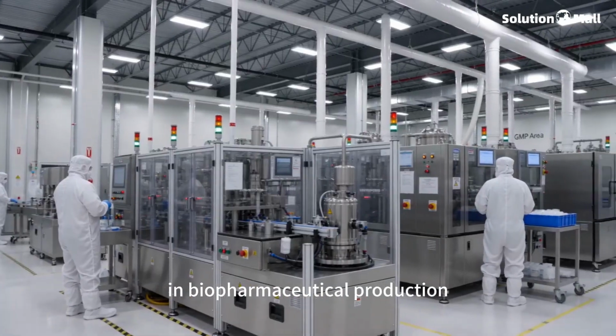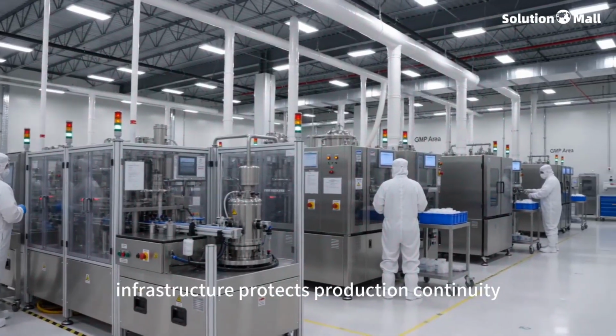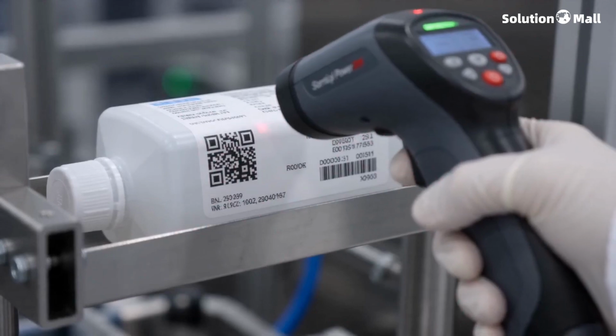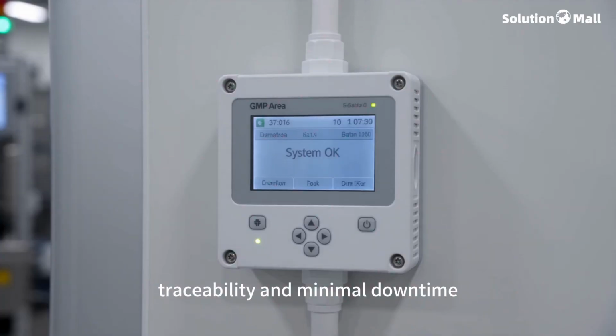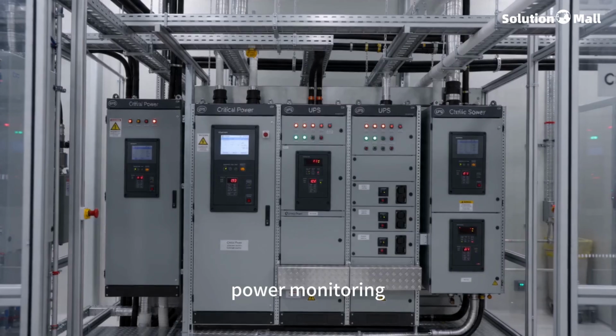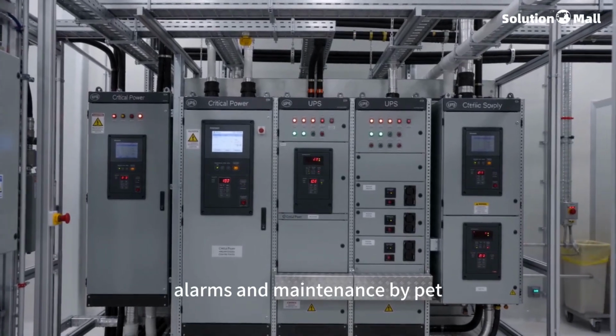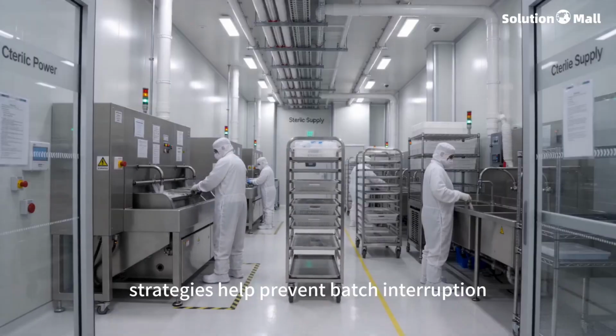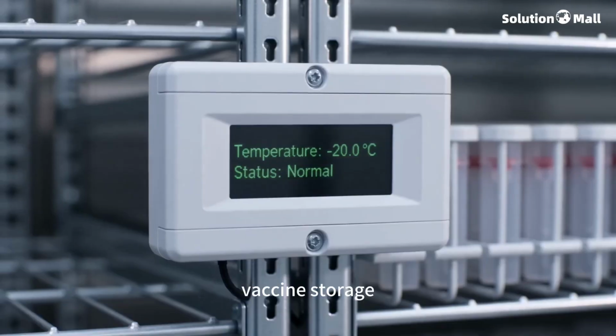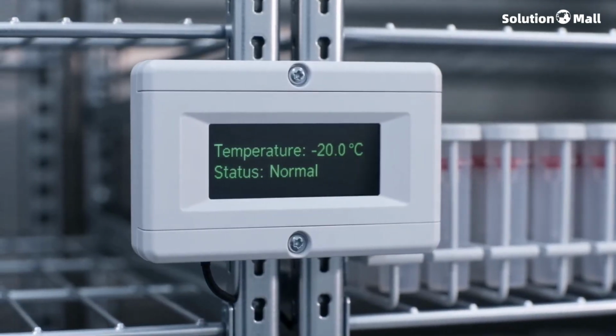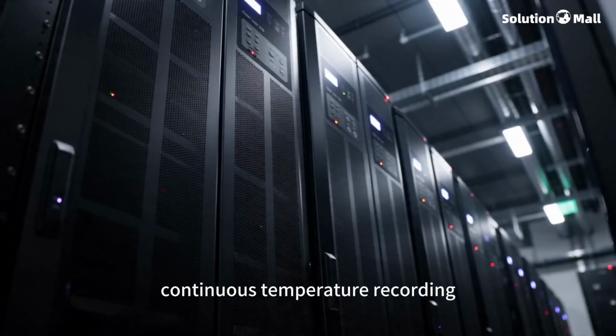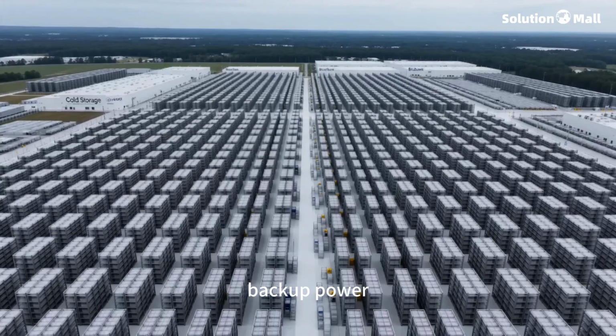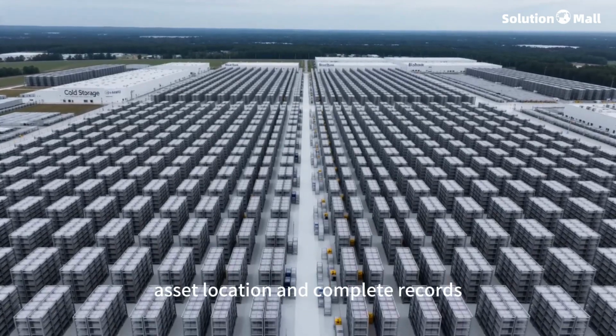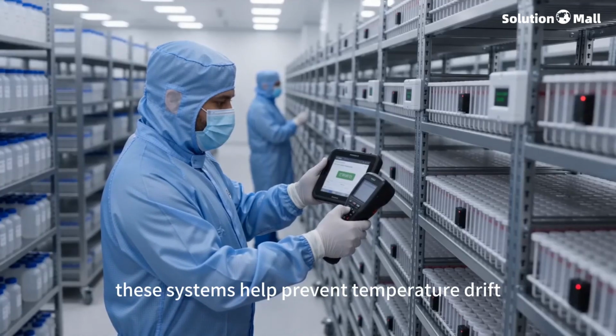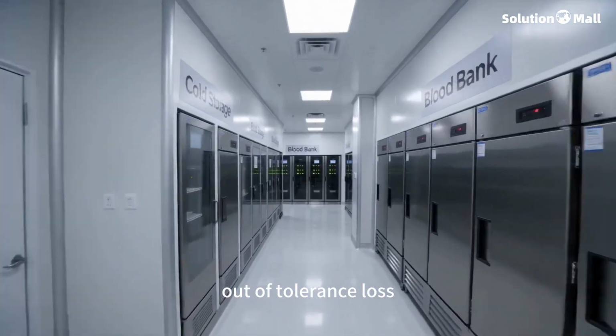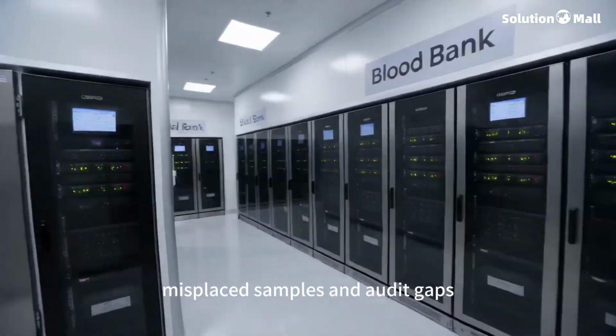In biopharmaceutical production and sterilized support areas, infrastructure protects production continuity, environmental consistency, traceability, and minimal downtime. Power, monitoring, alarms, and maintenance bypass strategies help prevent batch interruption, deviation, and incomplete records. Vaccine storage, drug cold rooms, blood banks, and biobanks require continuous temperature recording, backup power, remote alarms, asset location, and complete records. These systems help prevent temperature drift, audit-related loss, misplaced samples, and audit gaps.